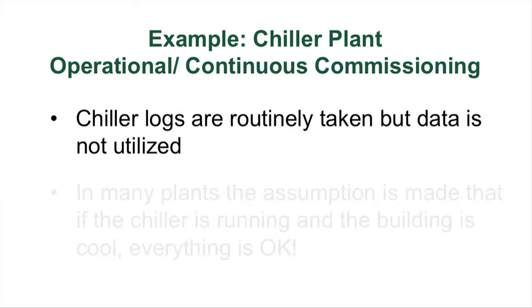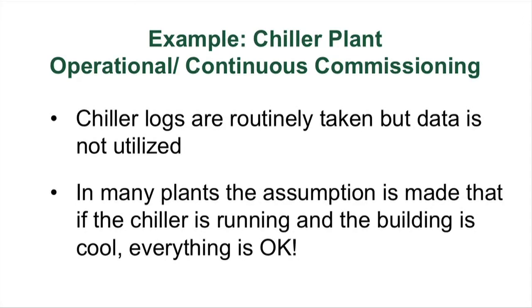So one example we'll look at is a sample chiller plant. In this plant, as in many plants, chiller logs are routinely taken, but the data is not utilized. It's simply written on a clipboard that's hanging by the chiller. And also, in many plants, the assumption is made that the chiller's running, the building is cool, everything's fine. That could be a chiller, it could be any other piece of equipment.